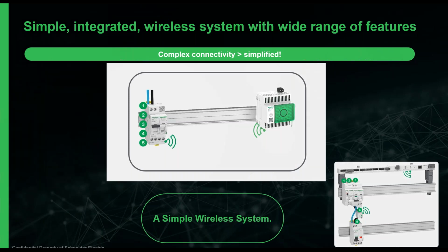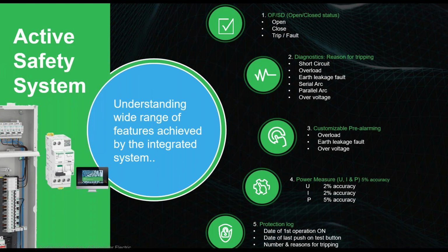What does it mean in terms of the data that we now have the ability to access because of the connected layers? We've now got the visibility to understand the open, closed, or trip and fault status of that circuit. Secondly, we can have diagnostics or the reasons for tripping. So we can, for the first time, understand from a remote location if there was a short circuit, or an overload, or earth leakage, or serial arc, parallel arc, or overvoltage.